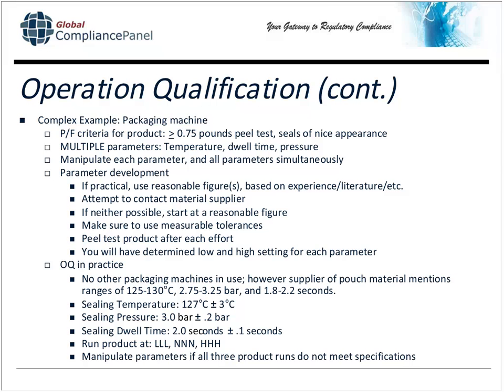In this hypothetical, the supplier of the pouch material mentions specific ranges that he's heard anecdotally. So the sealing temperature is 127 plus or minus 3. The pressure is 3 bar plus or minus 0.2, and the dwell time is 2 plus or minus 0.1. You run them at all the low settings, all the nominal settings, and all the high settings. And if all 3 production runs do not meet specifications, you're going to manipulate the parameters until they do.